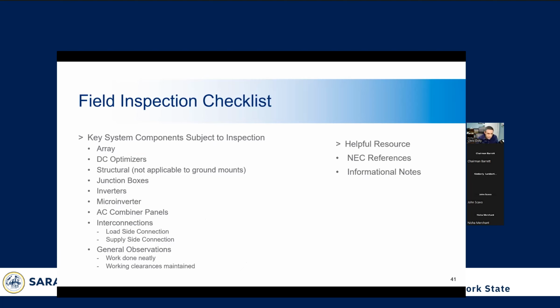All right, so the field inspection checklist provides an organized method of review, starting at one end of the system and going to the other. Typically, you would go from the array to the interconnection, or you could go backwards. It depends on your preference. But if you do it the same every time, that'll help you move through quickly each time and not make errors. If you're repeating the process, you just get better and better at it.